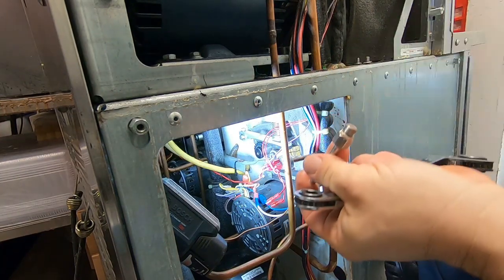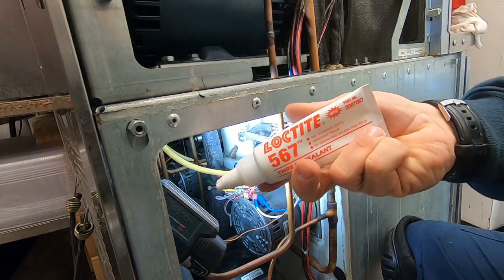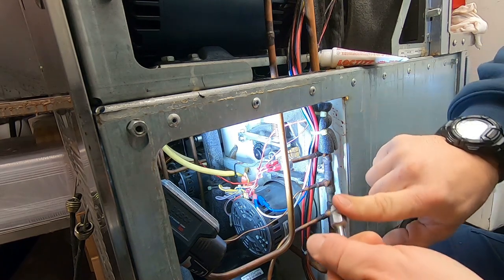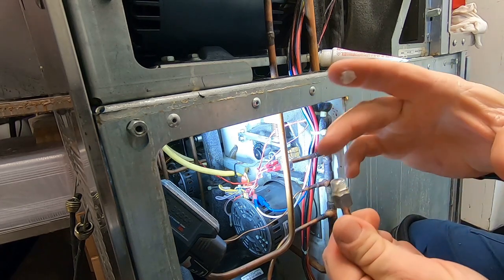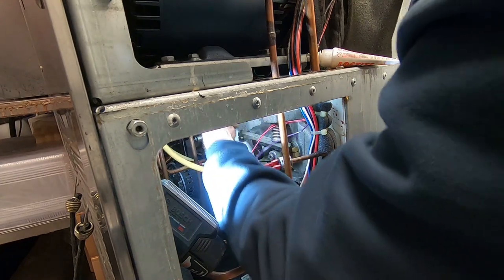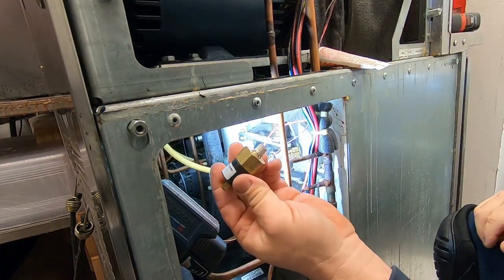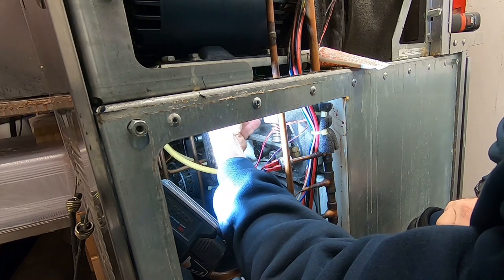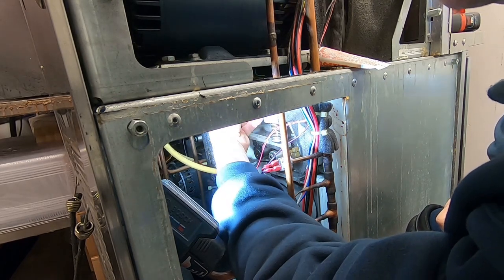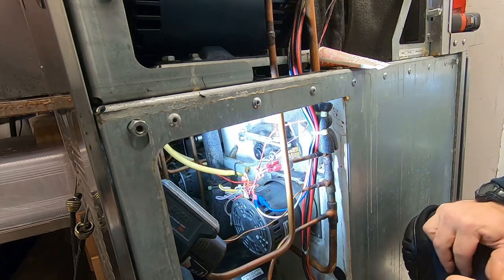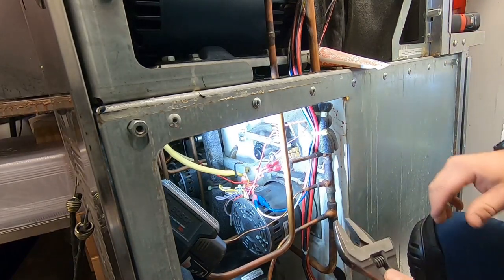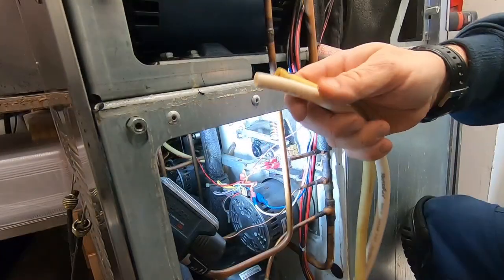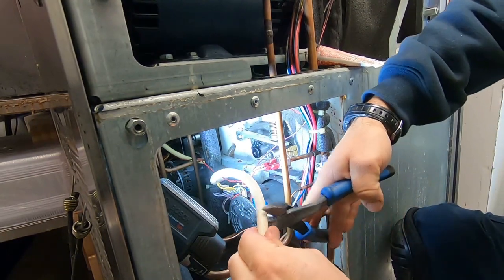Everything's open. We're just going to put a new hose on there. The Loctite I use is the 567. Go ahead and get that on here, just a little bit, just on the threads there. Make sure there's none on the inside. Here's your pressure switch. Basically it shuts the system down when it's got enough pressure in there. A lot of people don't realize that ice cream is 40% air and you inject air in there, whether it be with a force-fed machine like this where you're pressurizing it, or it's a gravity machine that'll have a carburetor and that'll meter it in there.